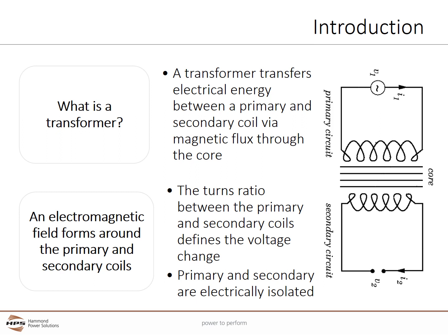Transformers work by converting electricity into an electromagnetic field, which is another form of energy. The transformer's core conducts the electromagnetic field like a wire conducts electric current. The electromagnetic field then induces a current onto the secondary coil, which converts the electromagnetic field back into electricity and thus achieves isolation. The turns ratio between the primary and secondary coils determines the voltage. In addition to electrical isolation, a transformer, like a reactor, provides impedance, although unlike a reactor, a transformer also limits short circuit current.